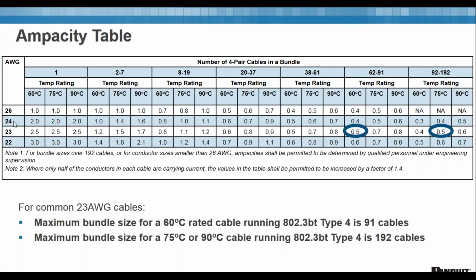Now, a common Cat 5e cable would be a 24 gauge cable, and you can see that with a Category 5e, if it's a 60 degree rated cable, your bundle is going to be limited to 61 cables, and for 75, your bundle is going to be 91. So you can see that this does have an impact. Everything we're telling you from TIA and on the performance side is important for getting your network to run. We're providing guidance, but if you're not meeting our guidance, you should still be passing data, and as long as everything's working, you're all good. What we're telling you here is code compliance. These are the rules you absolutely have to follow if people are enforcing that code.